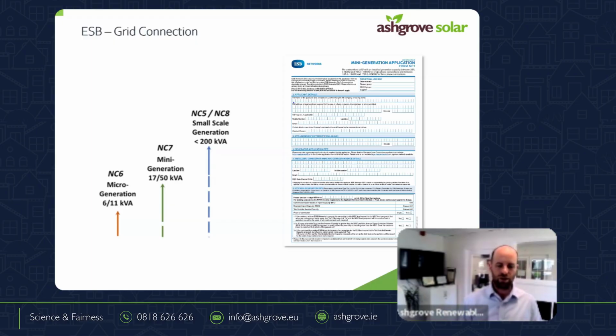So you never really want to be just above the bandwidth, or the grade. You don't want to be at 51 kilowatts and have to go for an NC8 - you're much better putting in a 50 kilowatt inverter. You can't convert as much electricity, but your capital costs are reduced significantly. Whereas if you're going for 150 kilowatts, it now makes sense to go for the larger NC8 application.